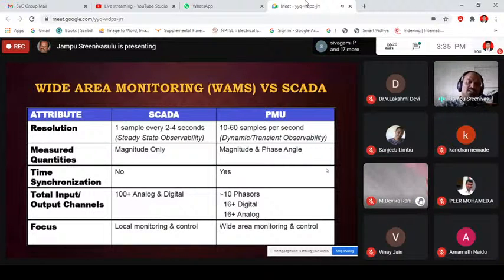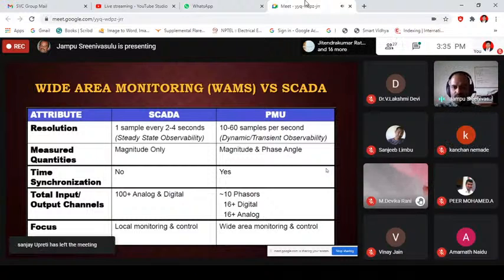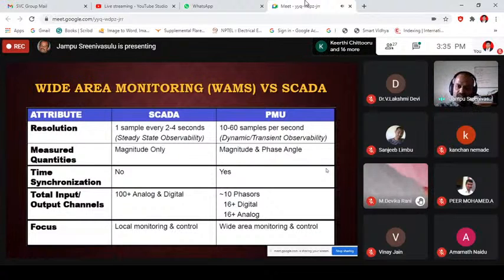With respect to resolution, SCADA gives one sample every 2 to 4 seconds, whereas a phasor measurement unit can capture 10 to 60 samples per second, which gives dynamic and transient observability. SCADA measures quantities only in terms of magnitude, whereas a phasor measurement unit can measure not only magnitude but also phase angle. Time synchronization is not possible with SCADA, whereas a phasor measurement unit maintains time synchronization.